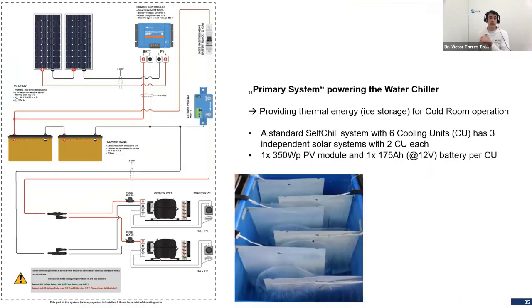Let's have a look in more detail at how a primary system is connected. So now we have here a primary system with 2 cooling units, 2 batteries, 2 PV panels, and a charge controller. So very simple. It's like a solar home system. PV panels and batteries are connected to the charge controller. Then we have a battery protect, because we use Victron charge controllers. And then we have the 2 cooling units that have a thermostat. The thermostats of the cooling units are to control the ice inside the water chiller.